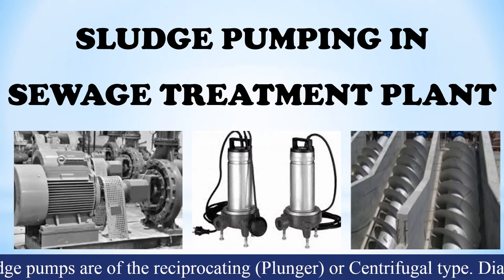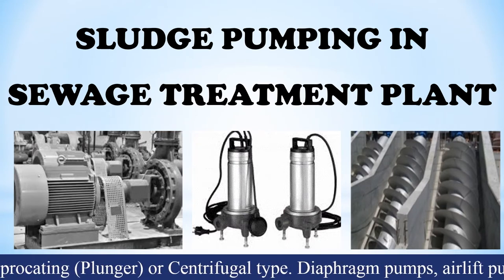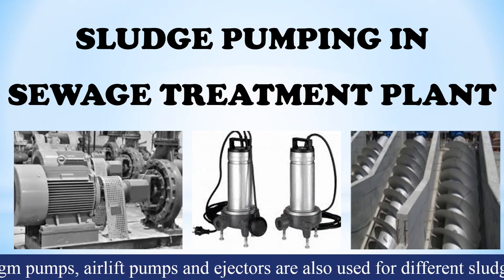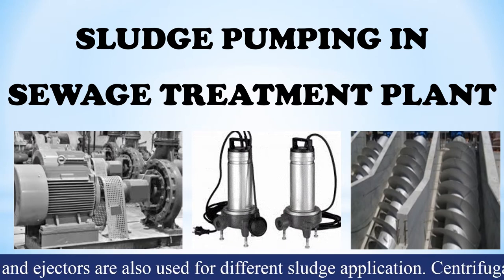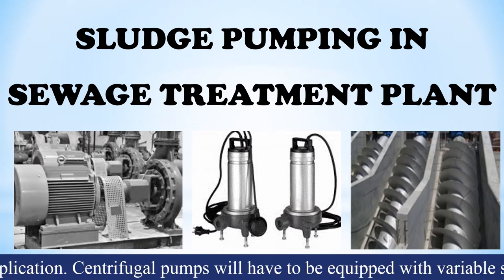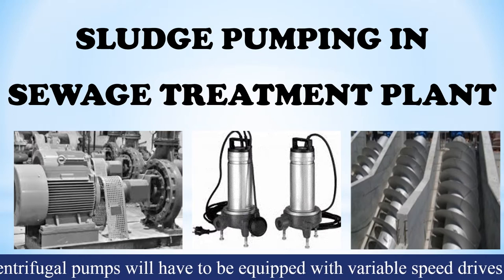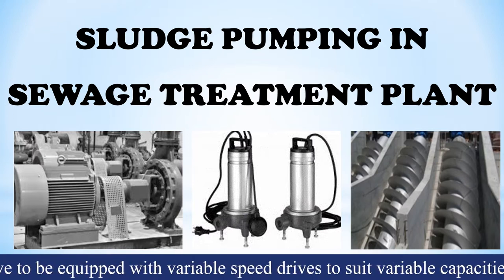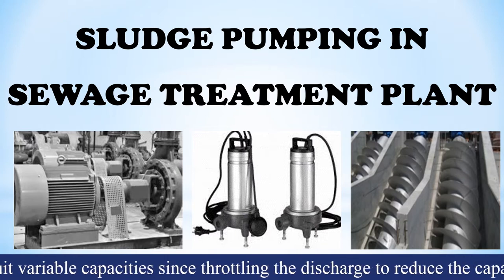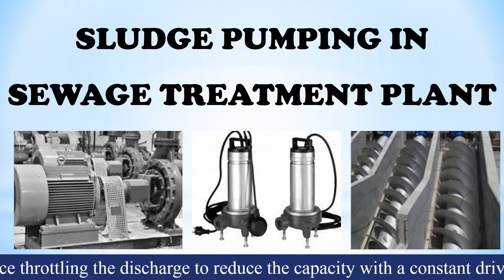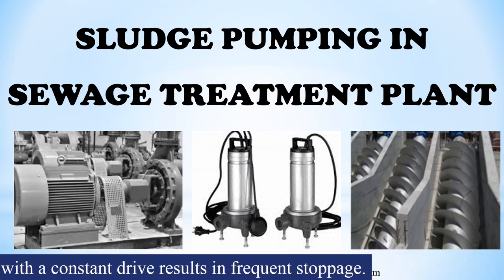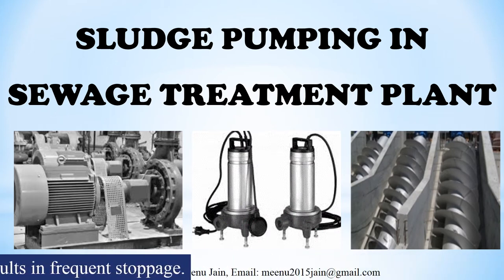Generally, sludge pumps are of reciprocating or centrifugal type. Diaphragm pumps, airlift pumps, and ejectors are also used for different sludge applications. Centrifugal pumps will have to be equipped with variable speed drives to suit variable capacity, since throttling the discharge to reduce the capacity with a constant drive results in frequent stoppage.